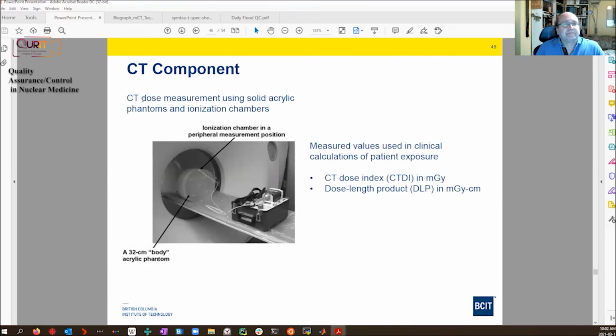And I want to mention the CT dose index. This is a way of measuring the amount of dose that is deposited in an acrylic cylinder for a certain set of CT exposure settings. So we control the kVp and the mA and the rotation speed and things like the pitch. And we want to measure regularly, for different CT settings, what the exposure is. And so we do these measurements and come up with something called a CT dose index.